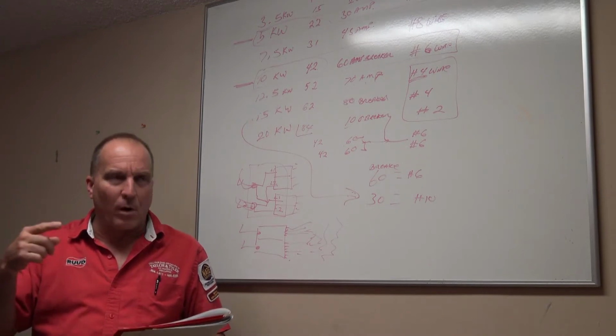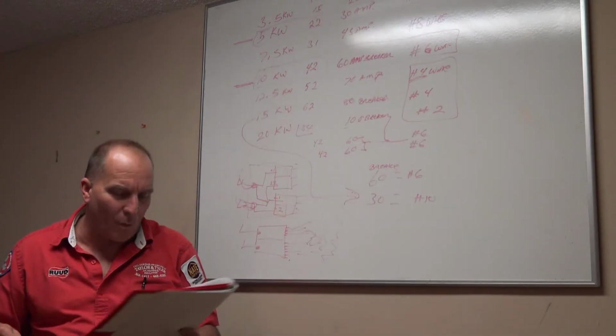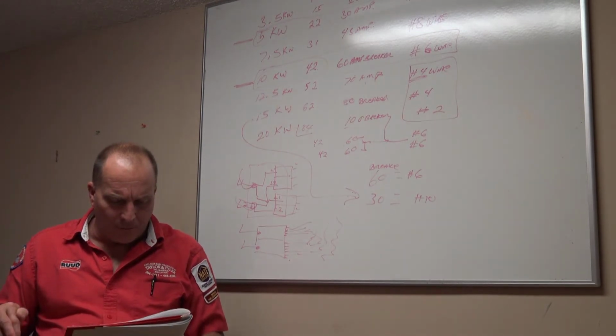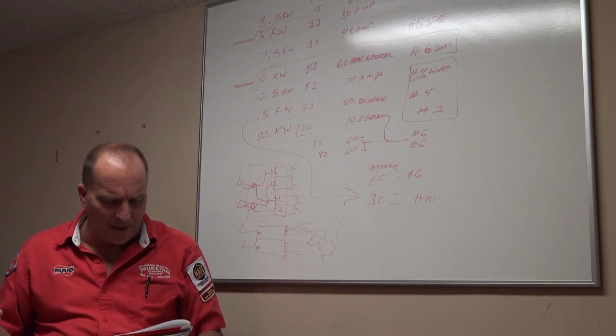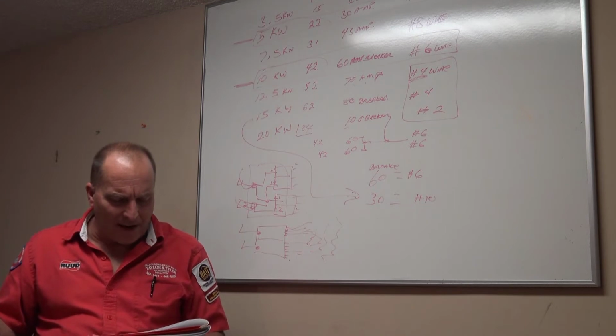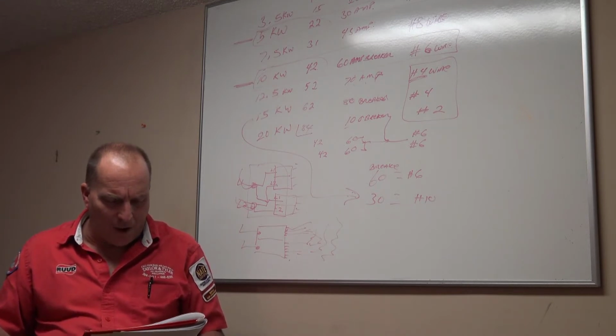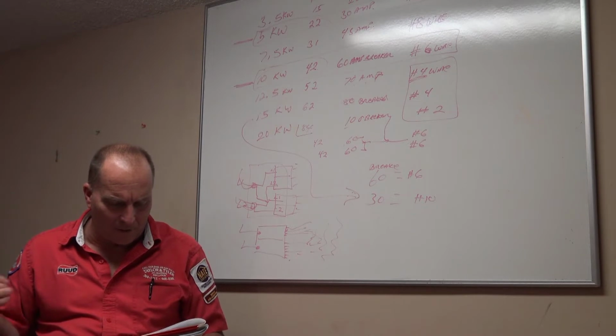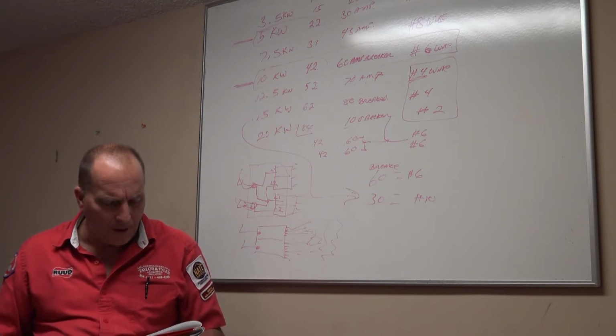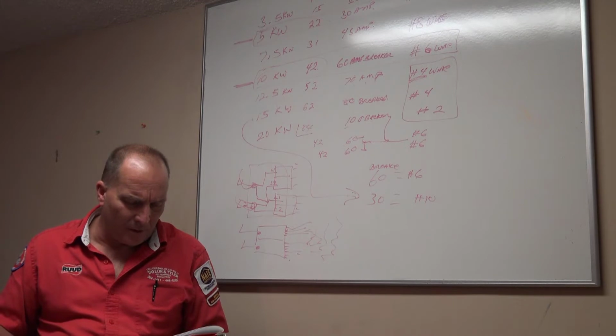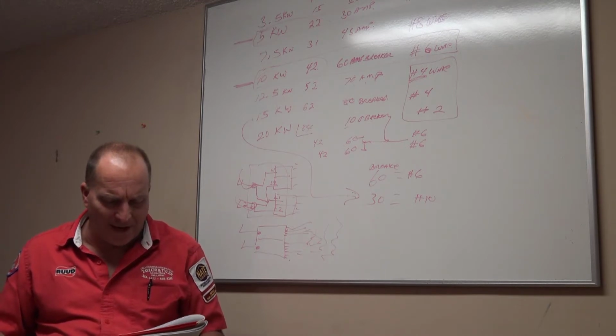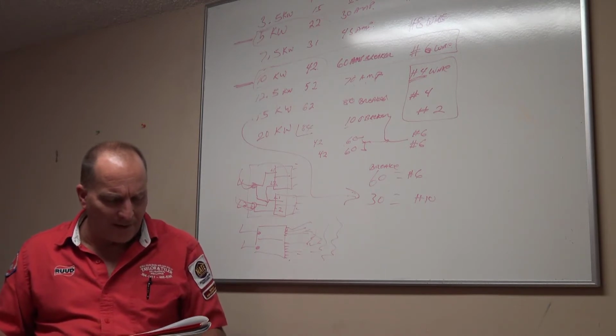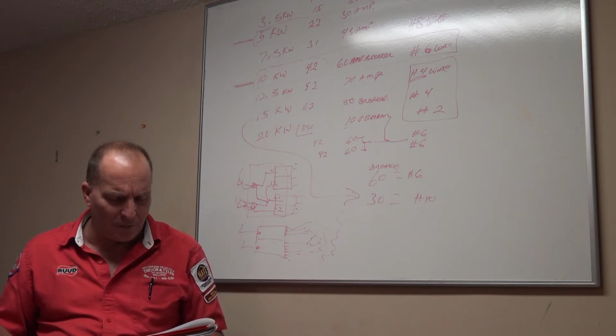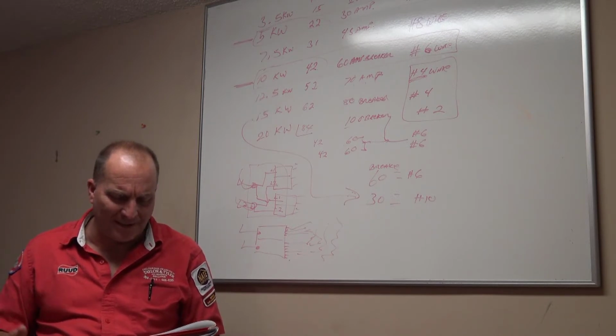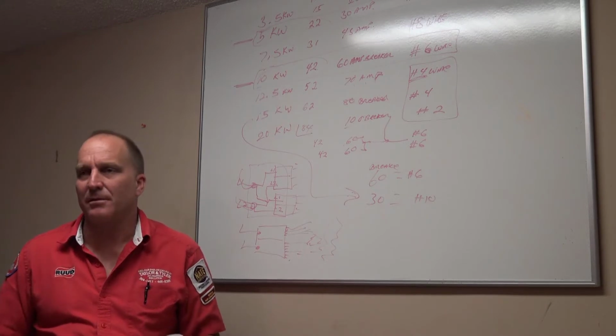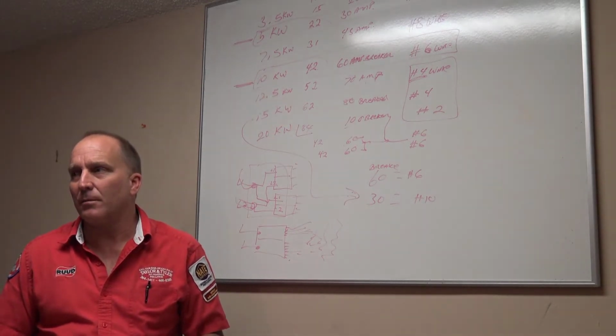See number 4, which we went over all of breaker sizes and wire sizes on number 4, for proper amps and wire sizes. OK means wire sizes, amps, condition of the wires are all OK, tightened all the lugs. Burn means wires are burned, could be bad connections, or wire size is wrong for the kW heat that is in the system. Check everything for proper size and amps and connections. I can't express that more and more and more.